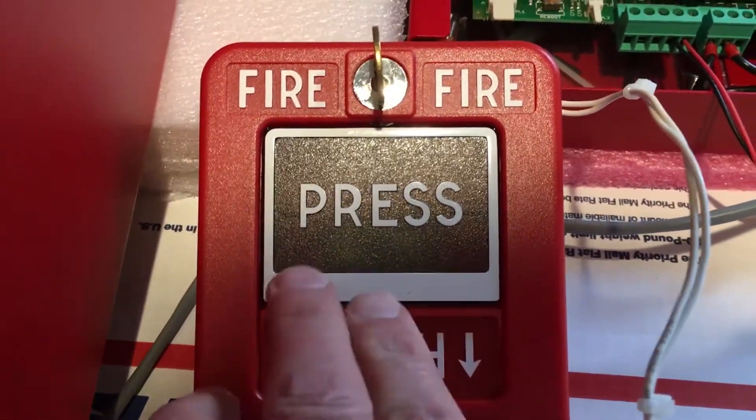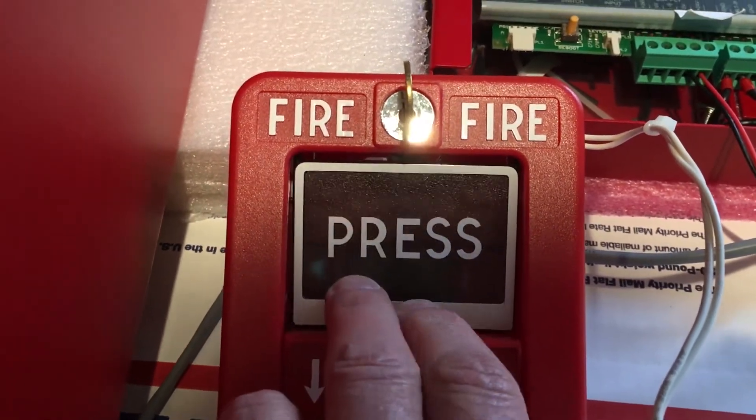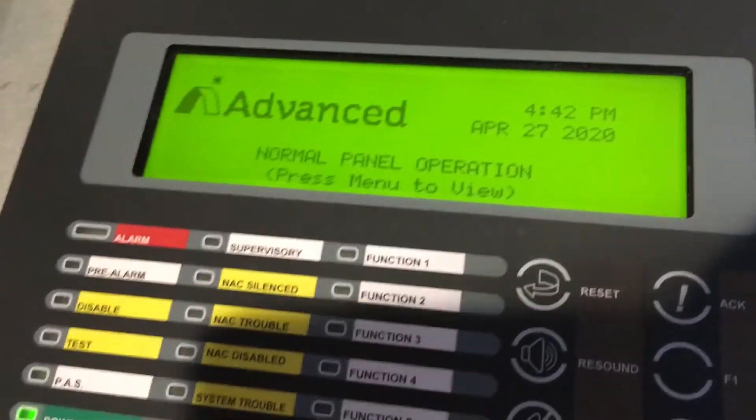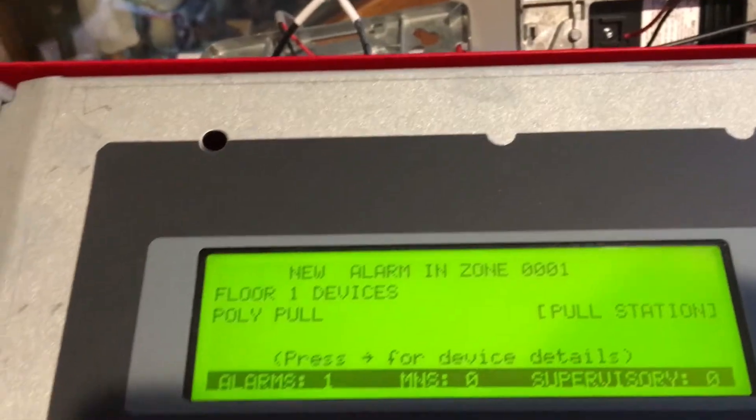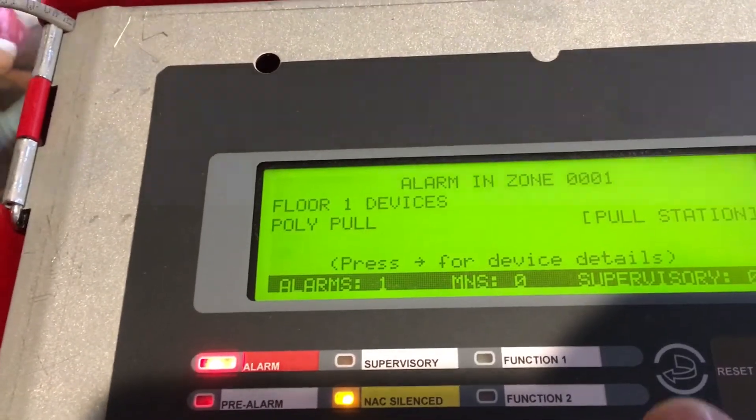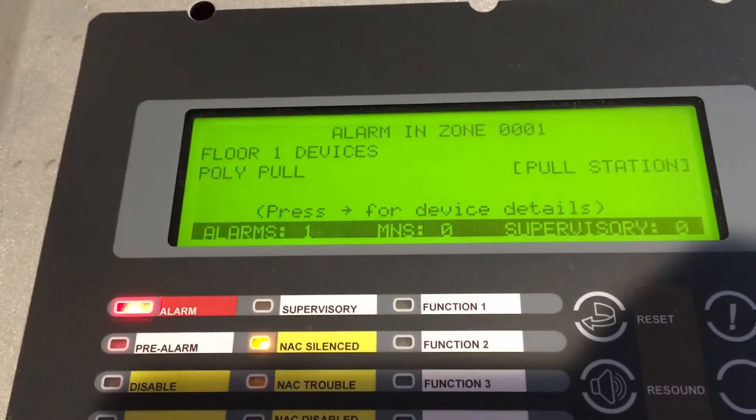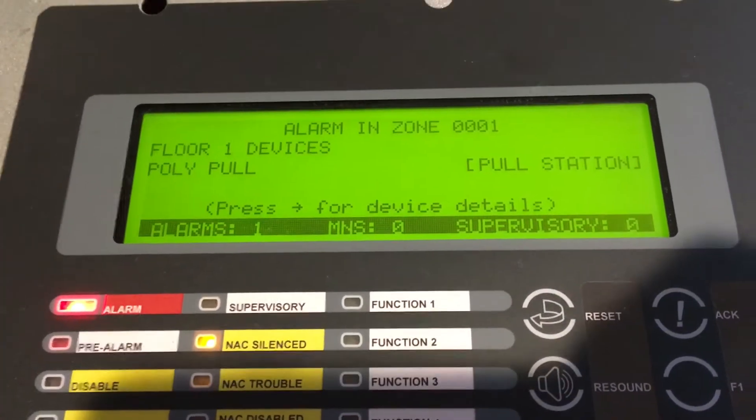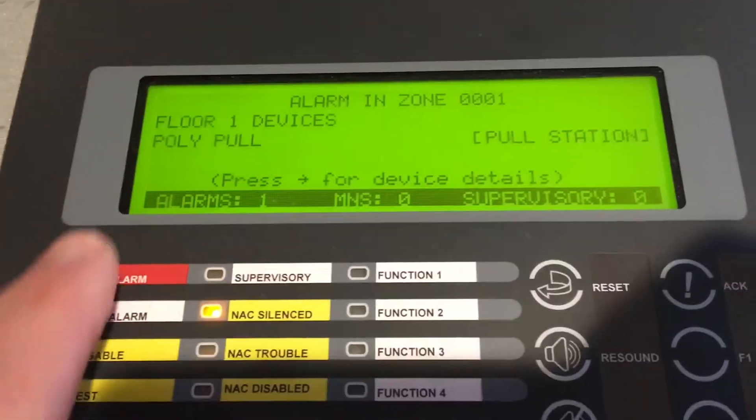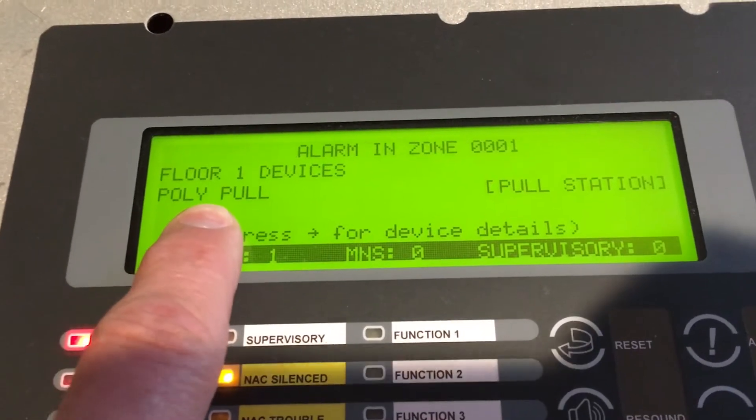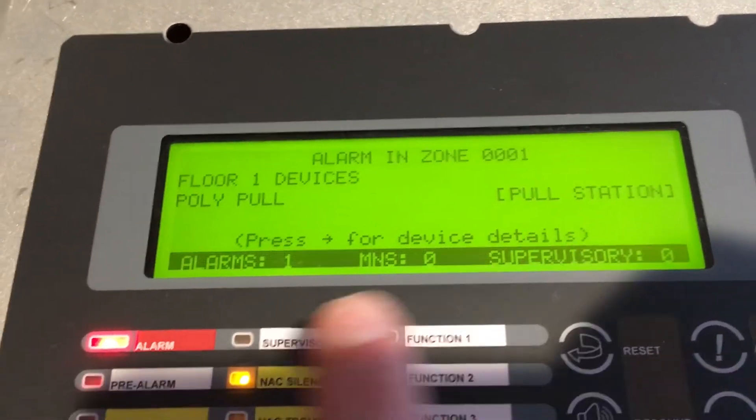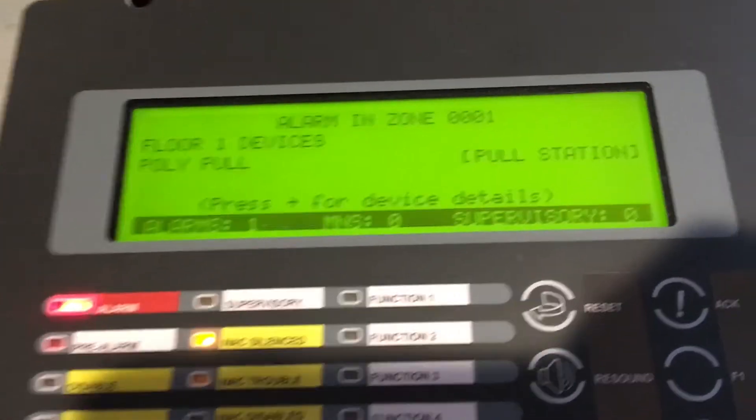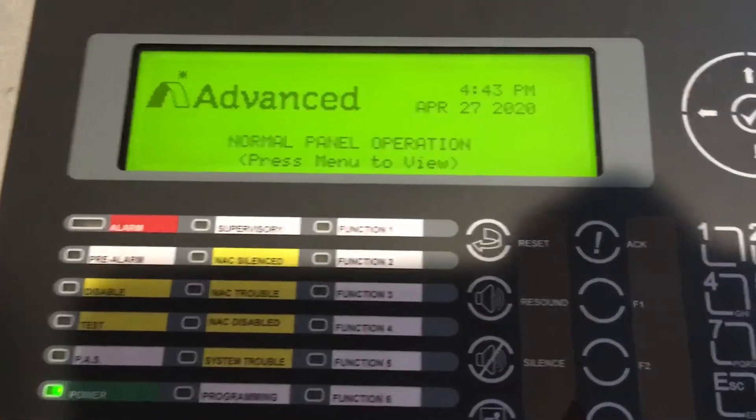We're looking at our pull station. I'm going to activate the pull station, and as I activate the pull station we'll look at the fire panel. As we can hear and see, the panel went into alarm. Some of the signals went off on the system. There's our first floor devices and it was the pull station that I activated. It says that it's a pull station and that it is in alarm.